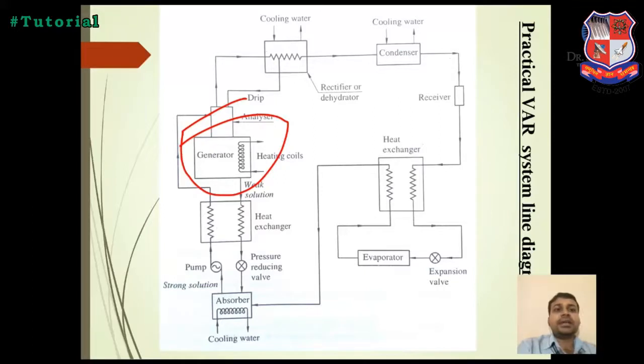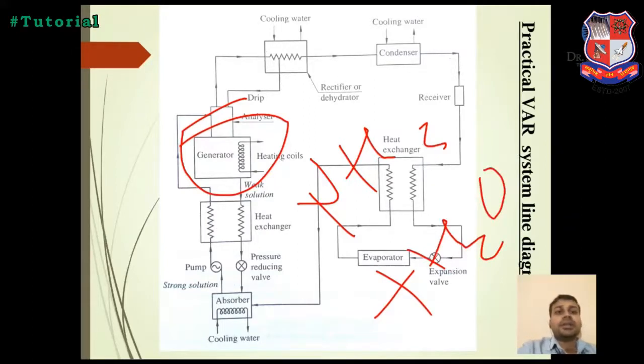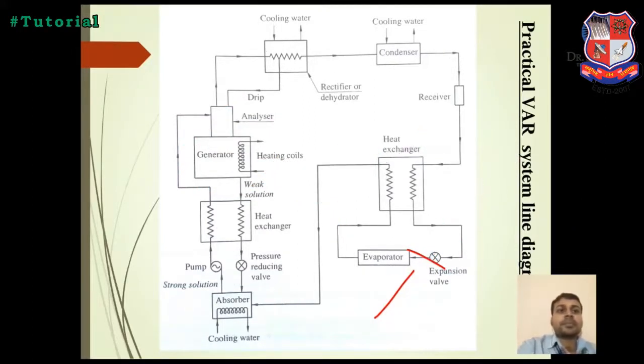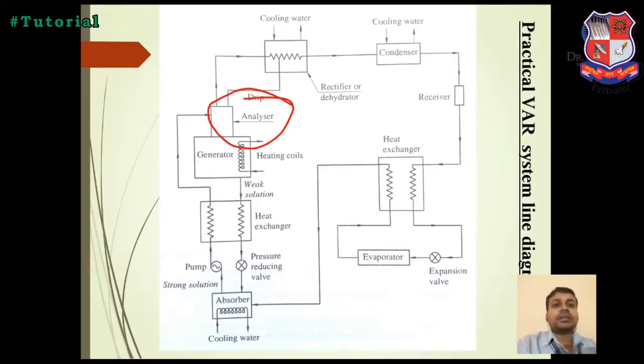There is an NH3 and H2O solution available in the generator. These two working fluids are there: one is the refrigerant NH3 and the second is H2O as the absorbent. These working fluids are in the generator, and the generator is given heat from an external source, and NH3 and H2O get vaporized. The next stage is the analyzer. The work of the analyzer is to separate the NH3 and H2O vapor.